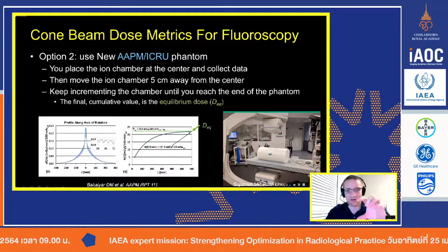So just a couple of hints here. How do you know? You can't see through this phantom, so it's really hard to know that you got it in the center. So obviously you'd push it to the center, you turn on your fluoro unit, put it into fluoro mode and actually see that it's centered. And you see the cable that comes out. Well, what I do is I actually physically take the cable and I put little markers on it every 5 centimeters or 10 centimeters.